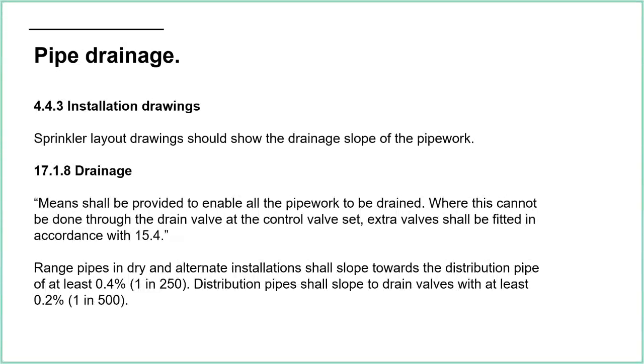Now, the easiest thing to do is to slope all of the pipes so that the water will naturally run back to the installation control valve. At the installation control valve, we have a main drain point, which is almost always hard piped into a drainage setup. So opening that up is a nice, easy way of draining. If you can imagine a tree, all of the branches are sloping back towards the trunk. That means all the water can come out of our alarm valve.